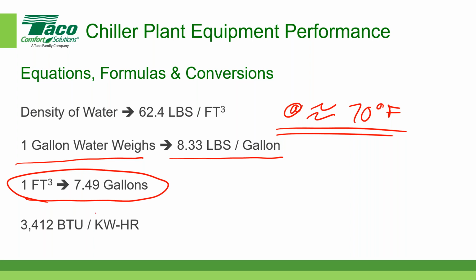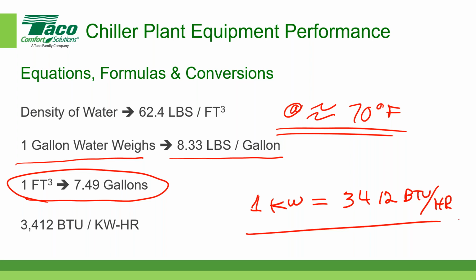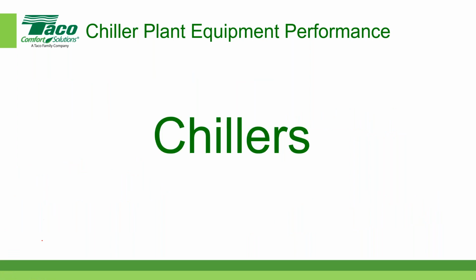And for the conversion for BTUs per kilowatt hour, there are 3,412 BTUs per kilowatt hour. So if I had, and I'm just going to make this very simple, 1 kW, then that 1 kW is equal to 3,412 BTUs per hour. Some useful formulas, they're good to know. Not going to spend a lot of time on it. Okay, let's move along here.